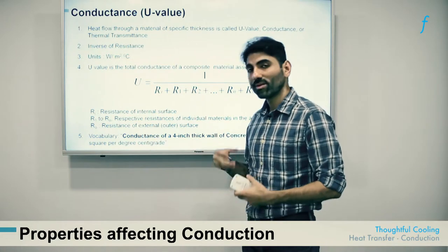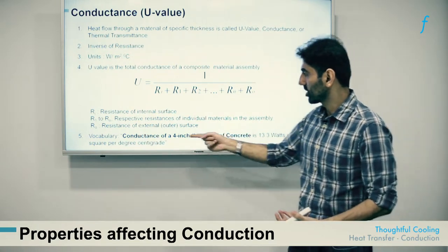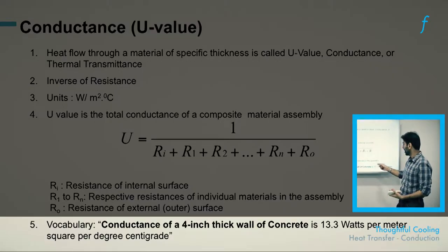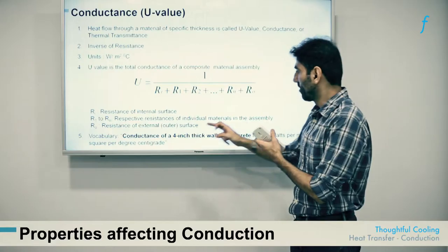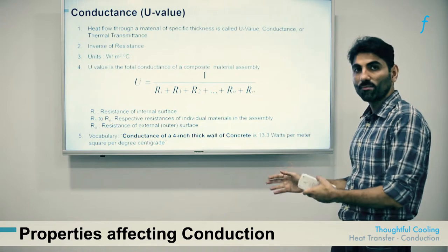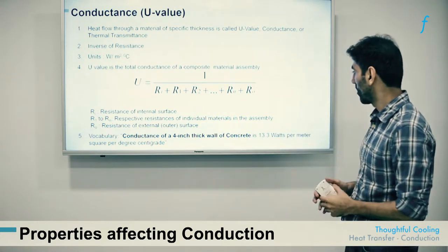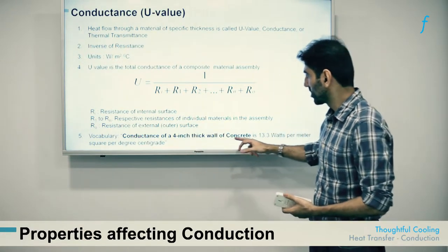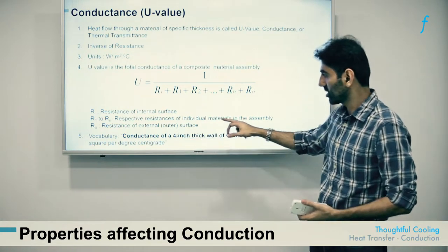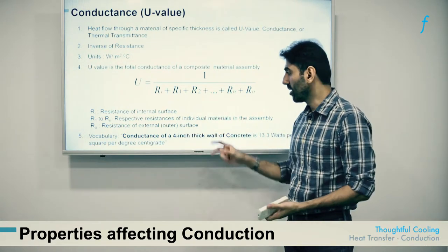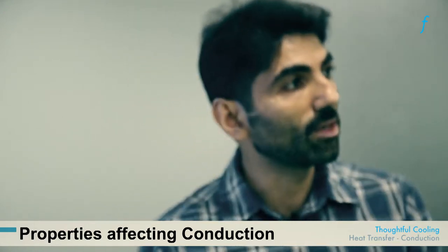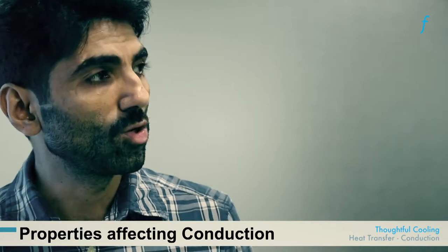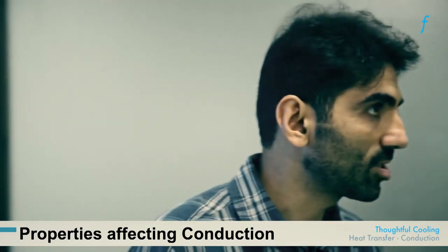In professional practice, one would say: 'the conductance of a 4-inch thick wall of concrete is 13.3 watts per meter square per degree centigrade,' which is 1 divided by the resistance value presented earlier. Conductance is inversely dependent on the thickness of the material — the conductance of an 8-inch wall of the same material would be half, because the resistance doubles as thickness doubles. Therefore, mentioning thickness is imperative when speaking of resistance or conductance.